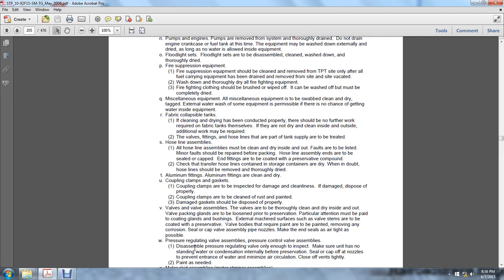Valve assemblies. The valves are to be thoroughly cleaned and dried inside and out. Valve packings and glands are to be loosened prior to preservation. Particular attention must be paid to the coating, glands, and bushings. External machine surfaces such as valve stems are to be coated with a preservative. Valve bodies that require paint are to be painted. Remove any corrosion. Seal or cap off the valve assembly pipe nozzle. Make the end seals as airtight as possible.